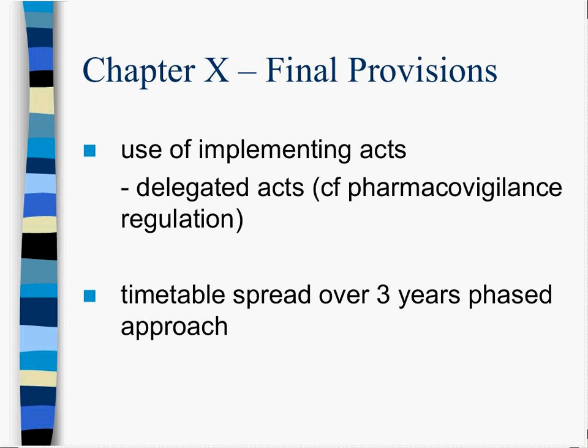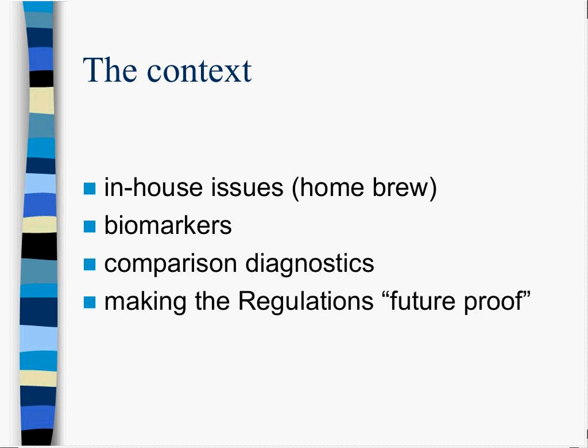As I said, there's considerable concordance with the MD regulation. Some of the key issues set out on this slide, though, are the improved supervision and better definition of when it's appropriate to use, or can use, an in-house derogation. And it's made clear that the in-house ability, what in the US is referred to as home brew, should only be used for less high-risk devices. The context here: the text looks at biomarkers, it looks at companion diagnostics, and the change in definition seeks to make the regulation future-proof.